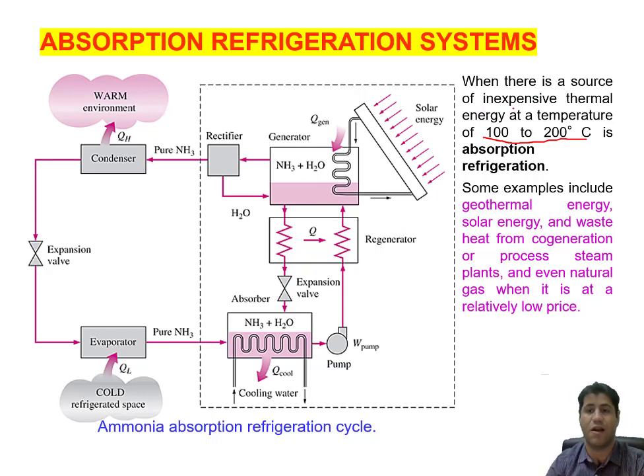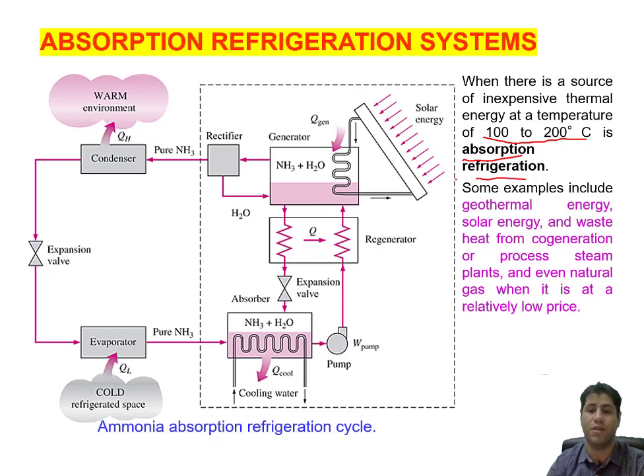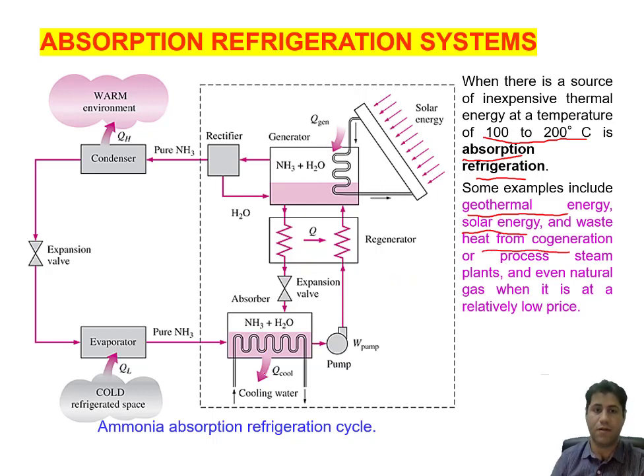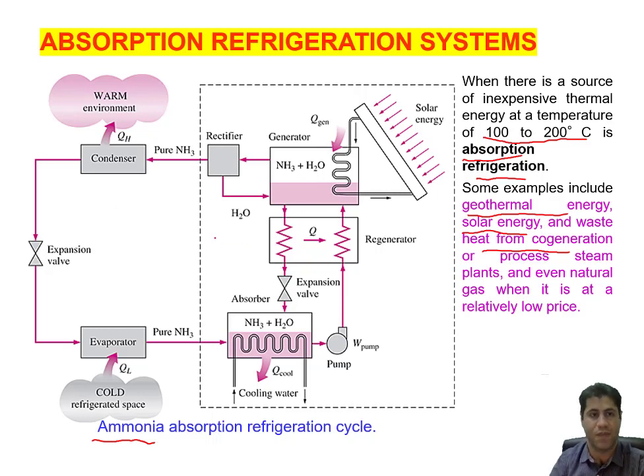If we have a source of inexpensive thermal energy at a temperature of 100 to 200 degrees Celsius, this absorption refrigeration system can be used — like geothermal energy, solar energy, waste heat from co-generation, and so on. Usually, we use ammonia as the working fluid in this cycle.